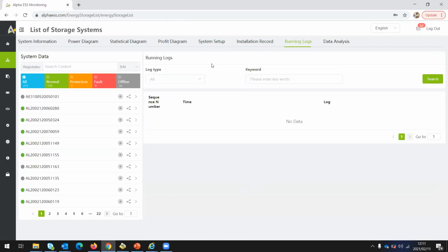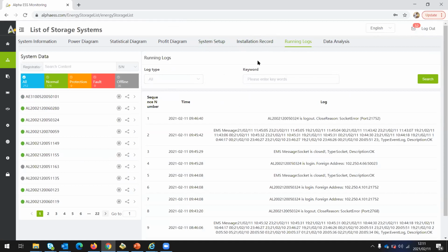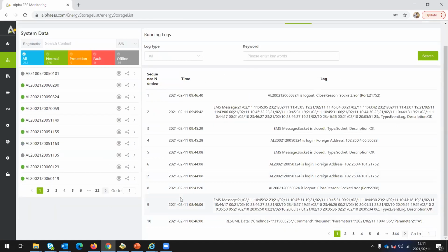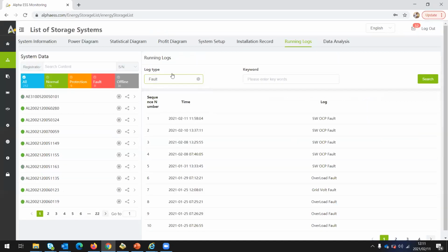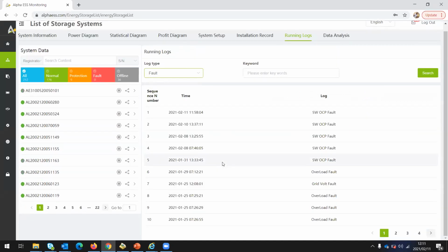And then on running info, this is a handy tool for installers. Basically it logs everything that was happening on the system. Even if you change a setting or someone logs in to view the system, it will log it. But the tool that we usually look at as installers is the fault. So on running info, you select fault, and you get to see the type, the fault codes, and the time period that it happened. In this case, you can see the system got an OCP fault.